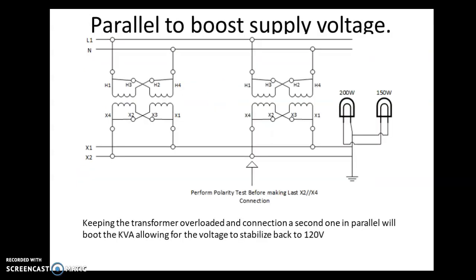Once we decide to parallel the transformer, a couple of things need to be taken close attention to. You will want to make sure that those transformers have the same kVA rating, they're of the same class, and that they have the same voltage ratings on the primary and secondary windings.